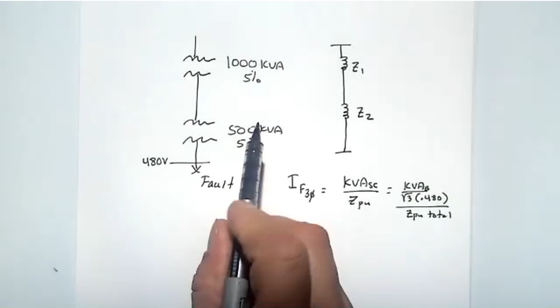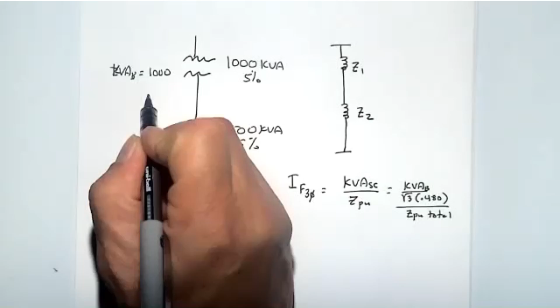So if I want to take my Z base, or my kVA base, and make it 1000, then Z1 is 5%, and Z2 is going to be bigger, as we said, it's more impedance at that base. So Z2 is the new base, which is 1000, divided by the rated, which is 500, times the 5% here. That gives us a total impedance of 10% for that one.